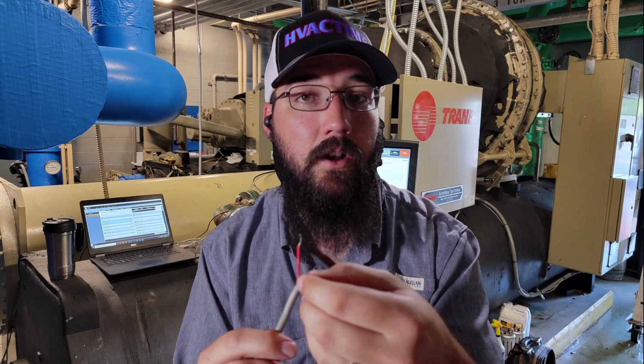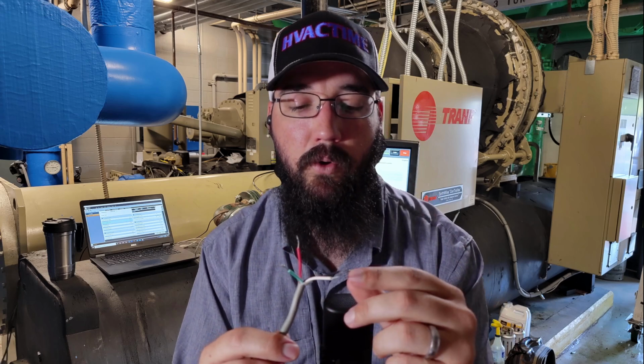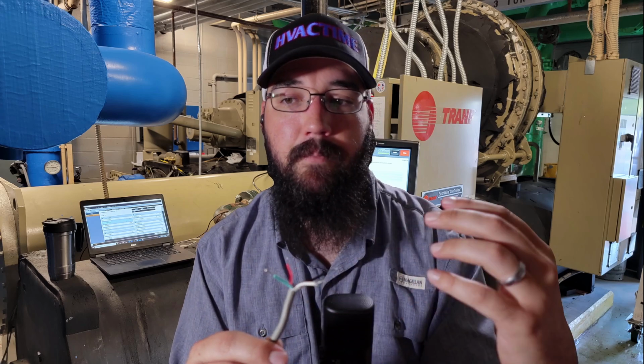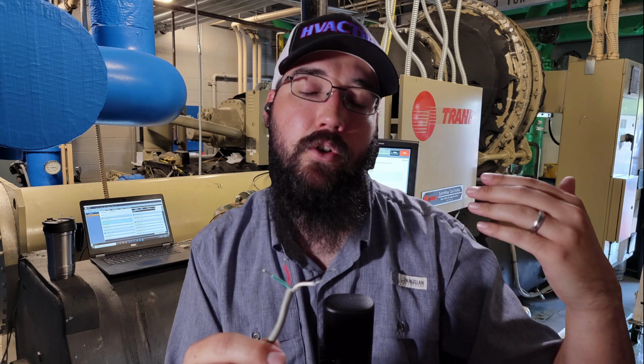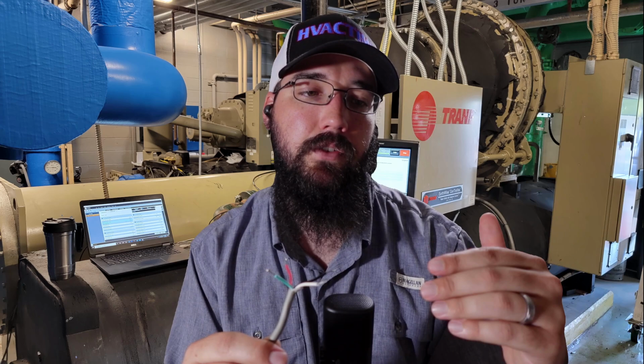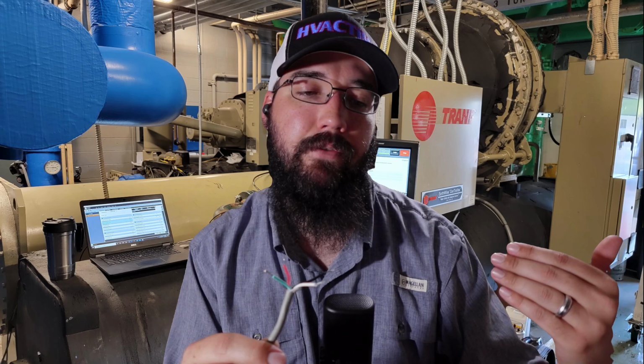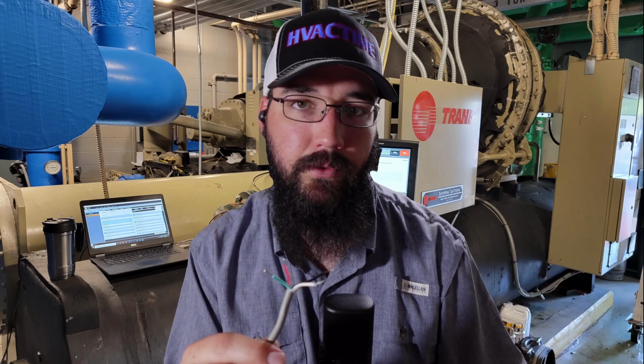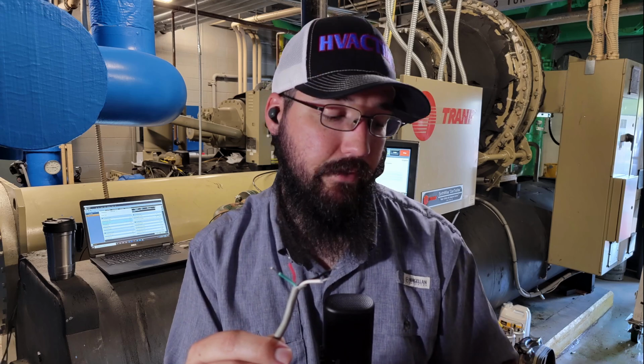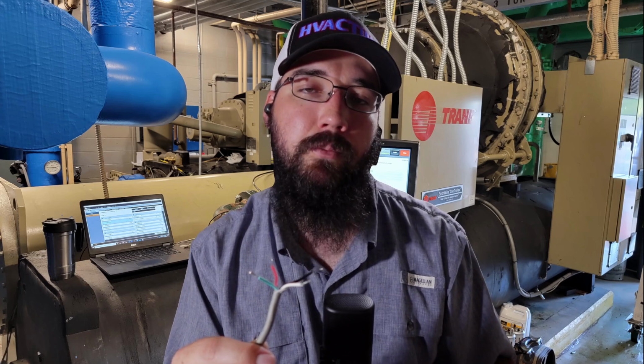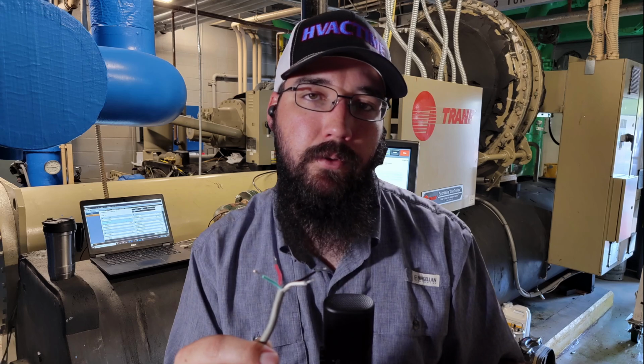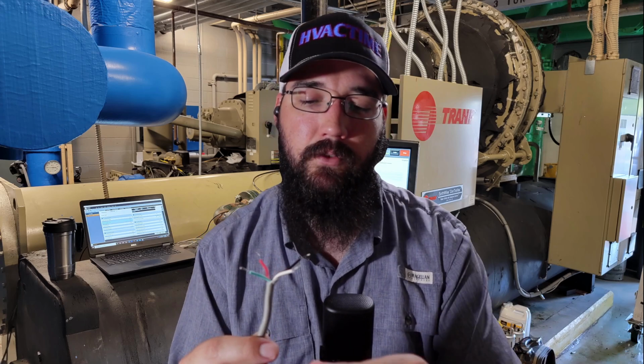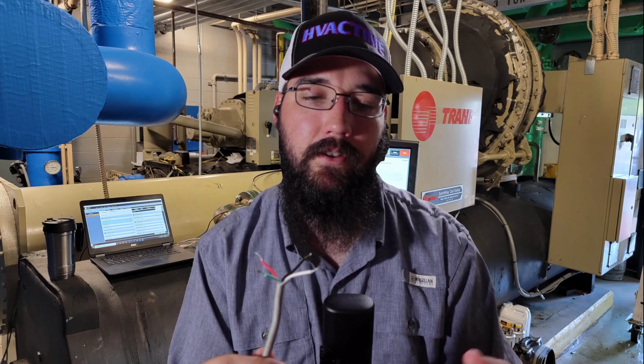Now, in the event that this was a 5-wire, we're just checking basic ohms here, and I'm not saying continuity, I mean ohms. Hopefully, most of us are familiar with that, but continuity is just stating that your ohm value is less than a certain amount. Most meters will show continuity if it's less than, say, 20 to 50 ohms. But the moment your ohm value gets above that, it won't beep continuity anymore, even though you may still have connection. So if you've got a coil that's running 80 ohms, you're not going to show continuity, even though it may be properly connected from an ohms perspective. Just be aware of that. So please don't rely on continuity for a test like this. That is not correct.